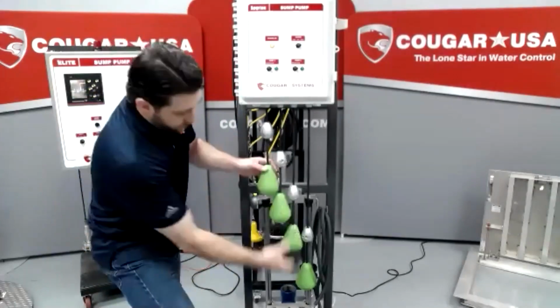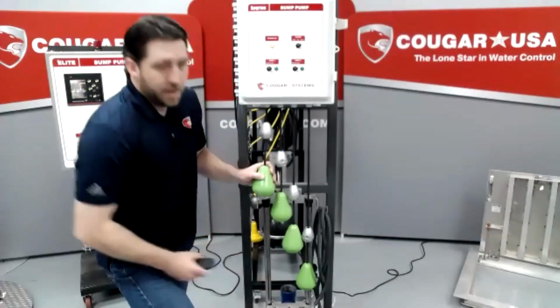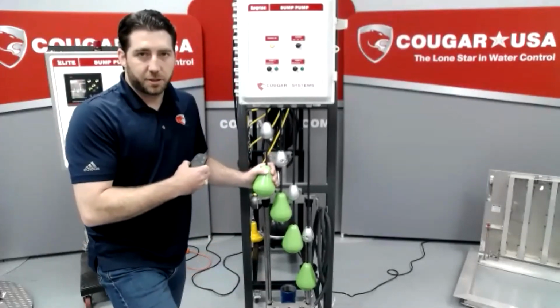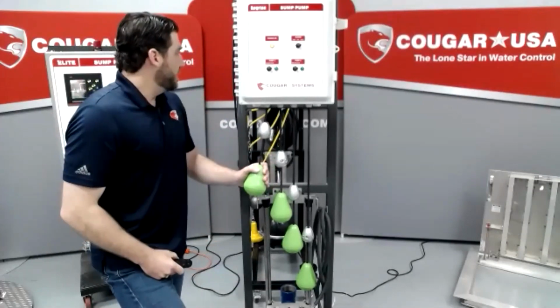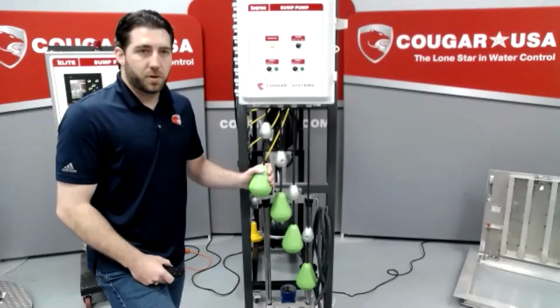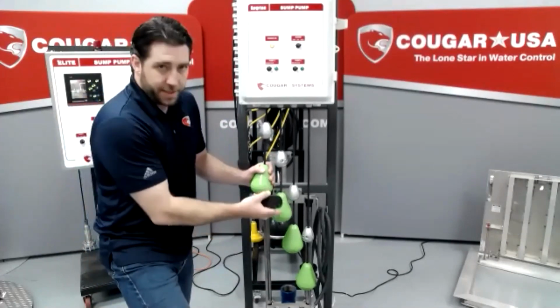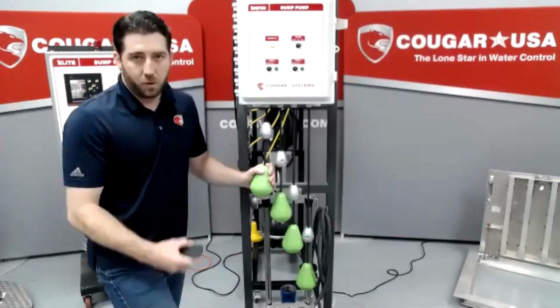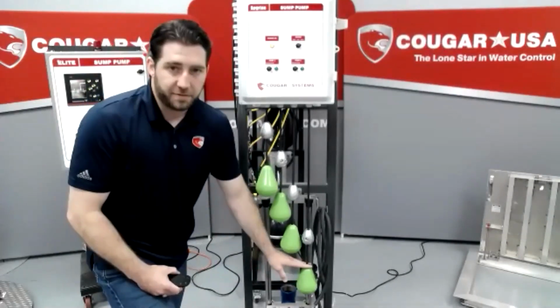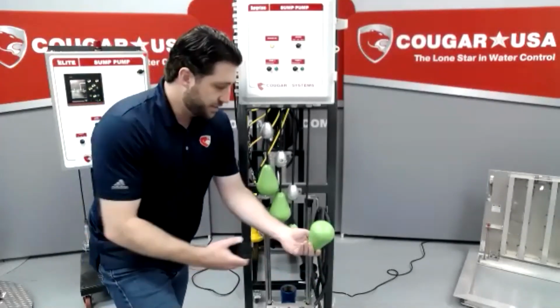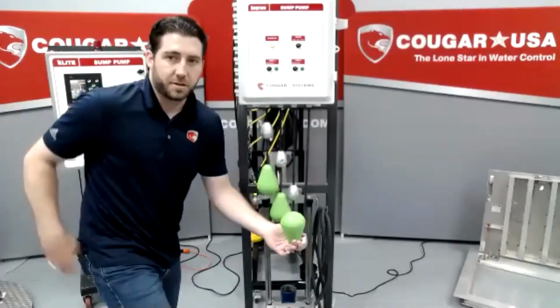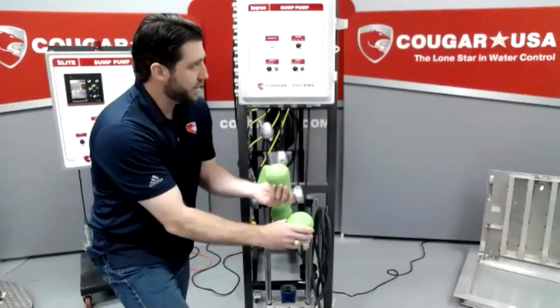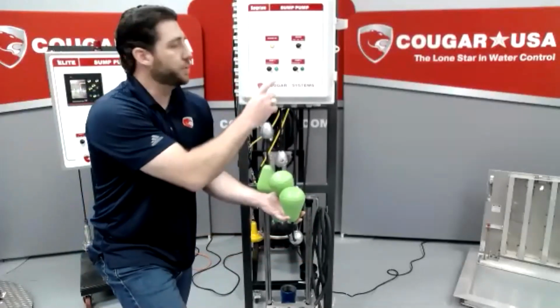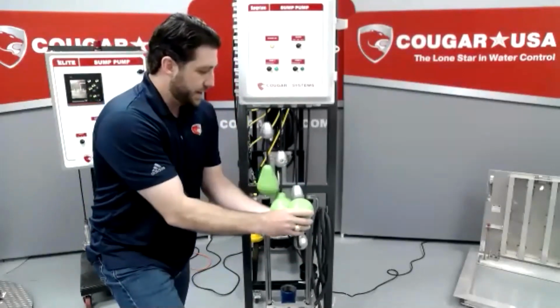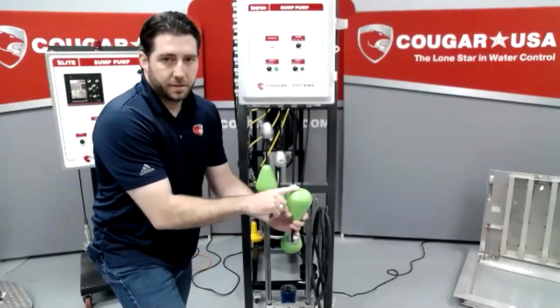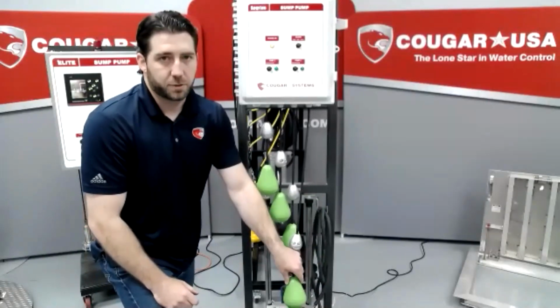Okay, so we have the 4-float switch set up here. I just want to point out on a relay logic style control panel, and with some of the PLC driven ones as well, when you have float switches like this in a sequence, a lot of times it's a holding circuit, meaning this bottom float switch has to come in first before you can start to move up the line and actually be able to turn pumps on and off. So that turned on my lead pump, and now when I go back down, this lead pump is going to stay on until this bottom float switch goes off.